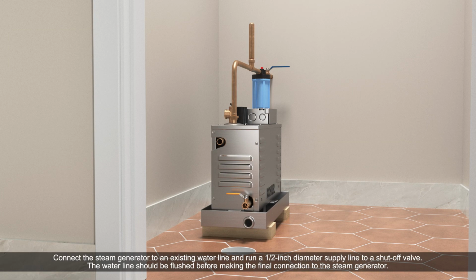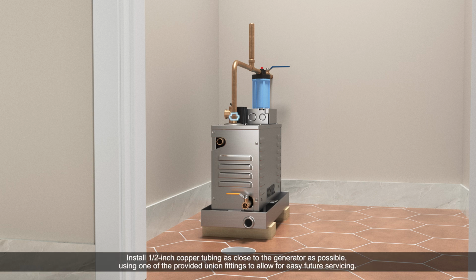Connect the steam generator to an existing water line and run a 1/2 inch diameter supply line to a shutoff valve. The water line should be flushed before making the final connection to the steam generator. Install 1/2 inch copper tubing as close to the generator as possible, using one of the provided union fittings to allow for easy future servicing.